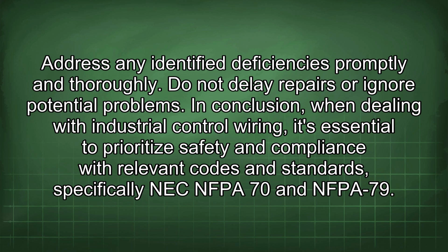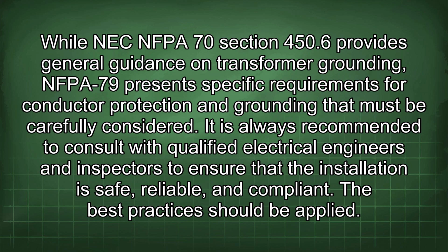In conclusion, when dealing with industrial control wiring, it's essential to prioritize safety and compliance with relevant codes and standards, specifically NEC NFPA 70 and NFPA 79. While NEC NFPA 70 Section 450.6 provides general guidance on transformer grounding, NFPA 79 presents specific requirements for conductor protection and grounding that must be carefully considered. It is always recommended to consult with qualified electrical engineers and inspectors to ensure that the installation is safe, reliable, and compliant. The best practices should be applied.